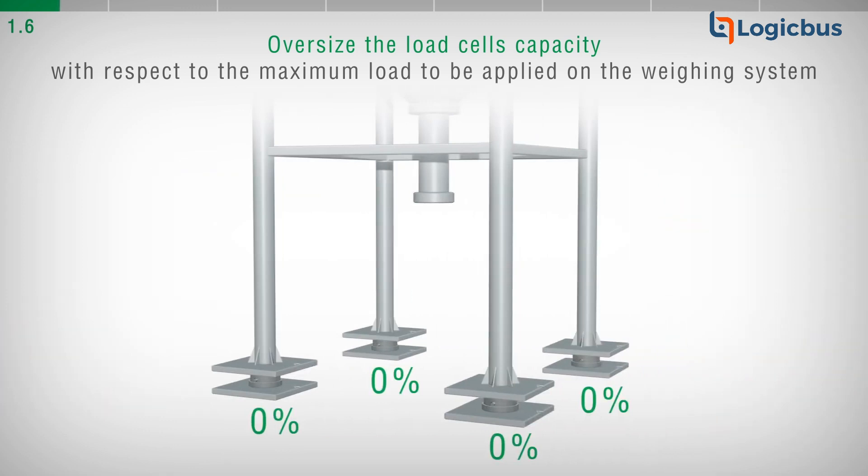In case of weighing structures with four supports, consider that the load will not be uniformly distributed and that 85-90% of the applied load will be distributed on just three supports.